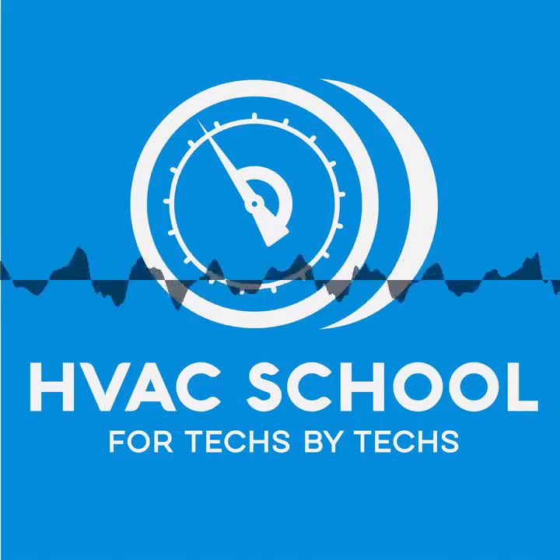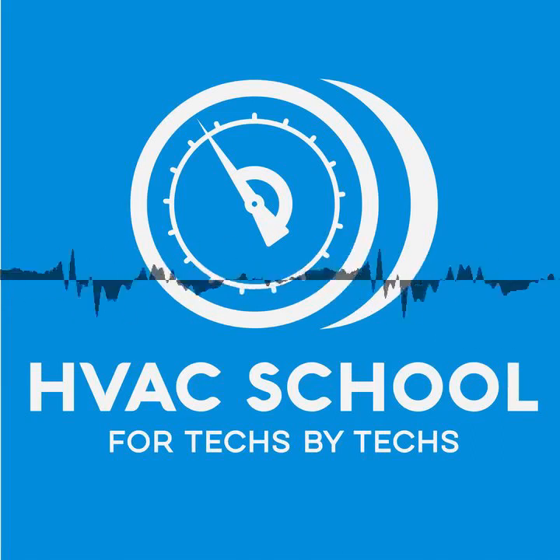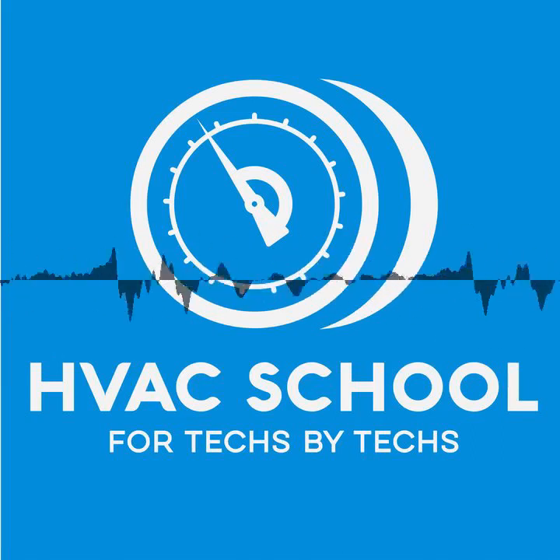You've got to clean all that off and then reapply it. But Nylog's good, very, very, very sparingly, especially keep it out of your vacuum gauge, because once you get Nylog on the thermistor, there's virtually no way of getting it off. Yeah, I've experienced that same thing. I've seen guys just use way too much and it gets all dirty and everything.